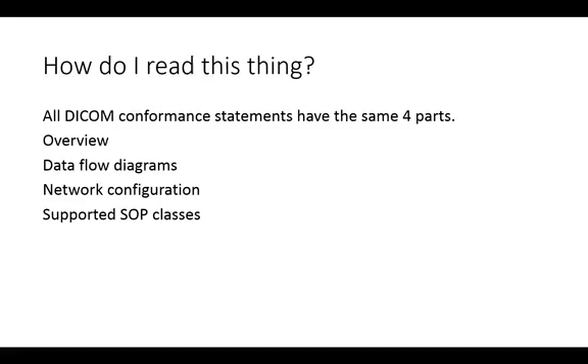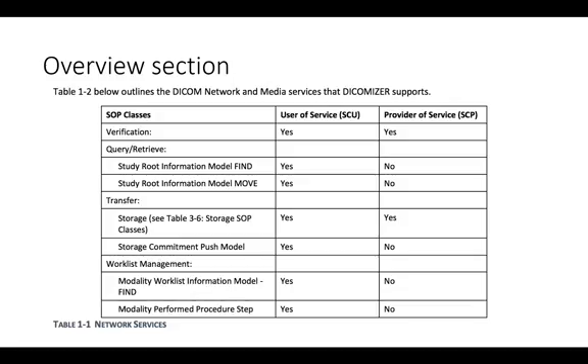This is an example of when you need to review the DICOM conformance statement. The great thing about the DICOM standard is that it's widely accepted and followed, so all DICOM conformance statements have the same basic parts. The overview section helps you answer two basic questions: what is this modality and what can it do? It lists the SOP classes and tells you whether it supports them as a user and/or provider.